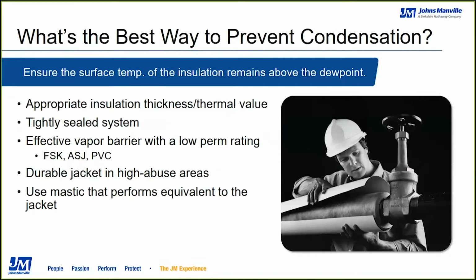And there are a number of factors that go into that, things like air temperature and humidity. Those are the main considerations, but it could also be wind if it's an outdoor application. And we'll talk about how you'll evaluate those various factors when designing a system in a moment. The second big consideration is you need to make sure the system is tightly sealed.